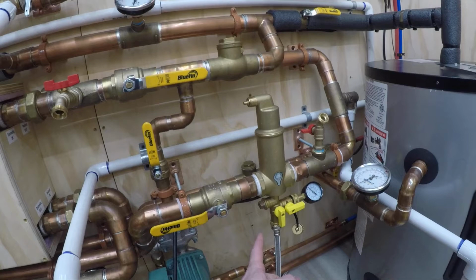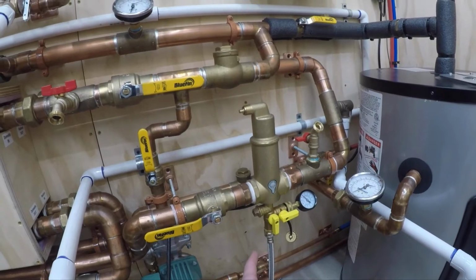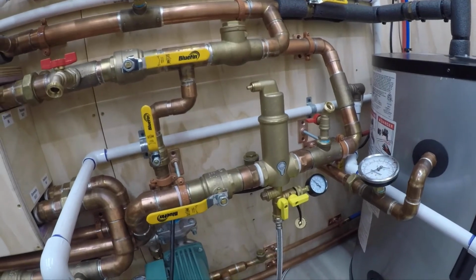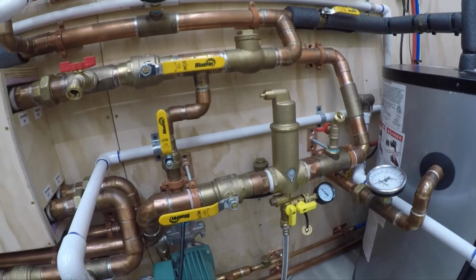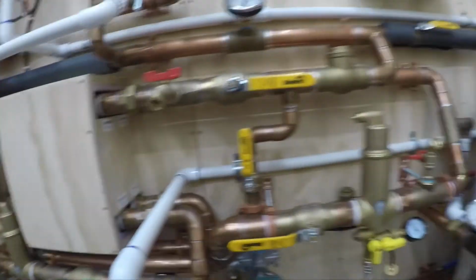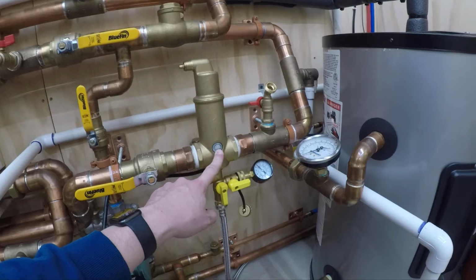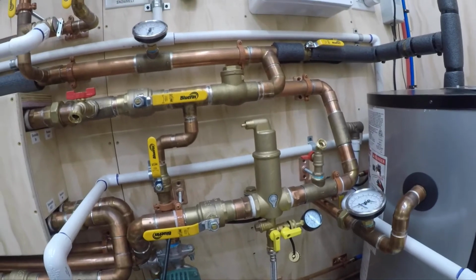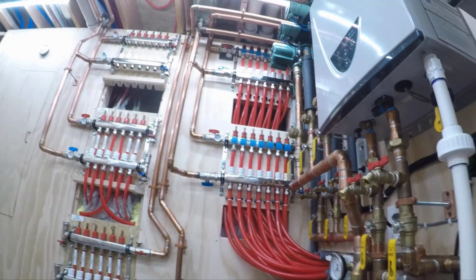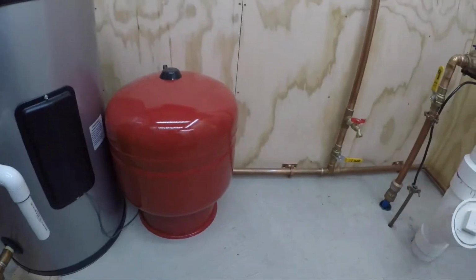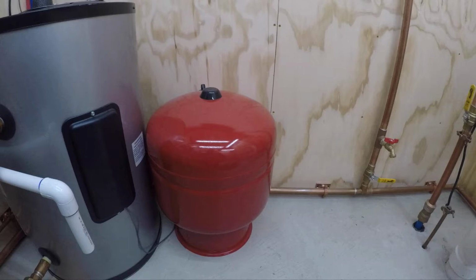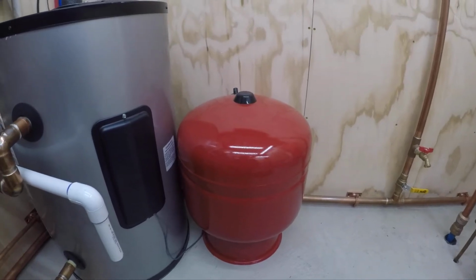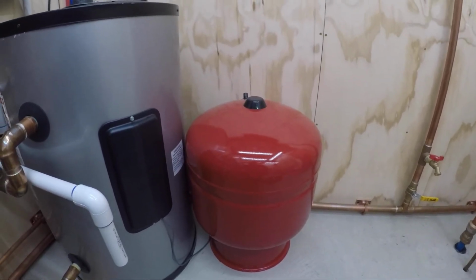Originally, I had, I think it's a 5-gallon EX30 expansion tank, similar to this, mounted right underneath the Spirovent. And then I realized that since I'm using glycol, and I did all the math for all the PEX and how much expansion I'm going to have, I need a bigger tank. So that's a RX60, and it's a red one because it's meant for glycol and radiant heat.